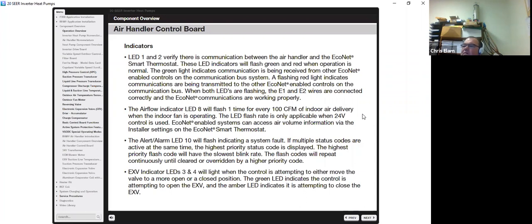The airflow LED will flash one time for every 100 CFM of airflow delivery when the indoor fan is operating. The LED rate is only applicable when 24 volt controls are used. You will not get that same flash when you're using EcoNet. From the EcoNet control, you can actually go in and check the status of whatever piece of equipment you're using. So if you're using an air handler or gas furnace, you can go to the status, and it will tell you what your RPM is, your CFM, and it will also give you your static pressure. That's very important, which we'll get into later as well.